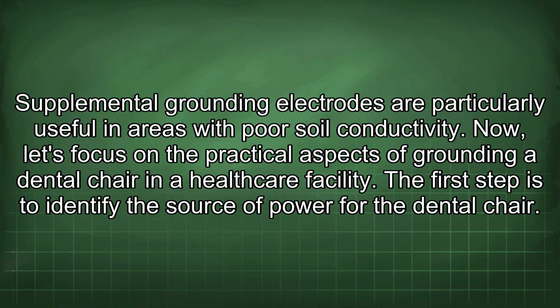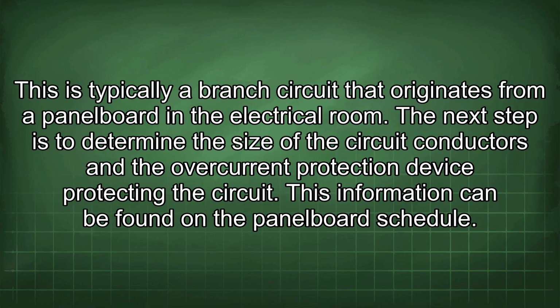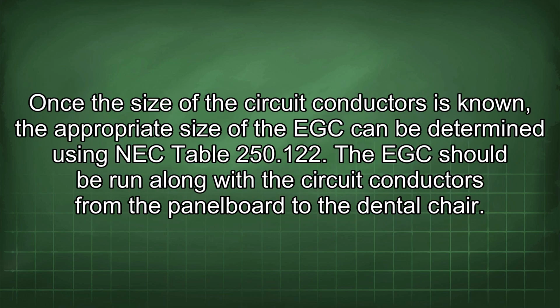Now, let's focus on the practical aspects of grounding a dental chair in a healthcare facility. The first step is to identify the source of power for the dental chair. This is typically a branch circuit that originates from a panel board in the electrical room. The next step is to determine the size of the circuit conductors and the overcurrent protection device protecting the circuit. This information can be found on the panel board schedule. Once the size of the circuit conductors is known, the appropriate size of the EGC can be determined using NEC Table 250.122. The EGC should be run along with the circuit conductors from the panel board to the dental chair.